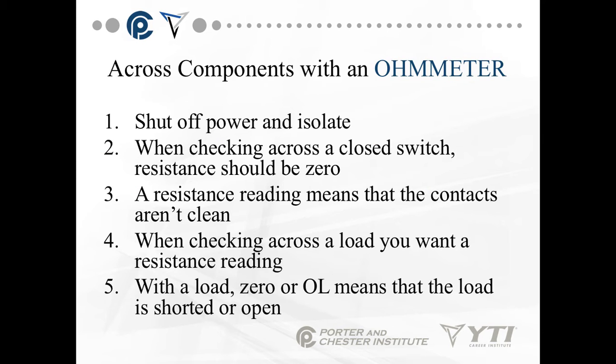The first thing you can do is check across all components with an ohmmeter. Basically what we're looking for is opens. What you do is shut off the power and isolate. When you're checking across a closed switch, resistance should be zero. A resistance reading means the contacts aren't clean.